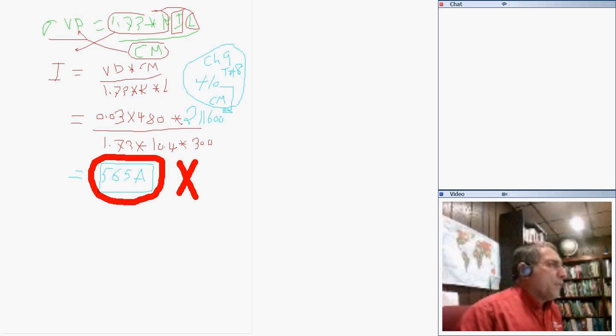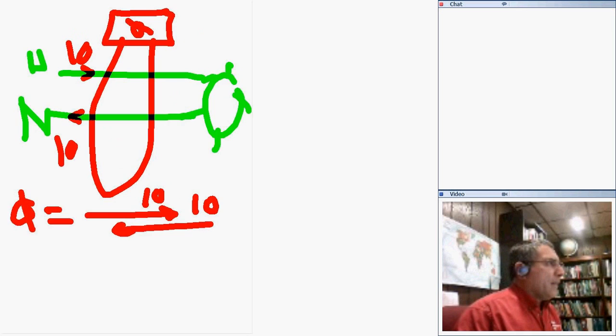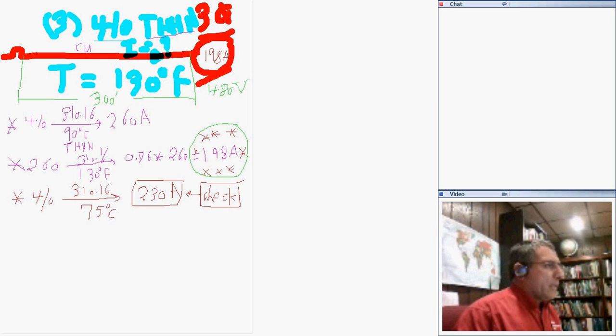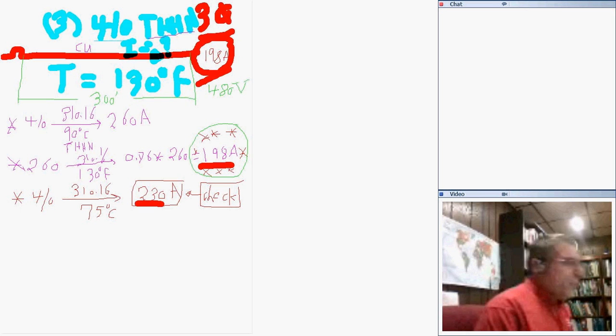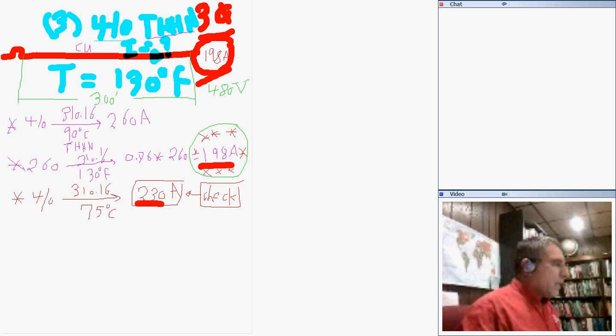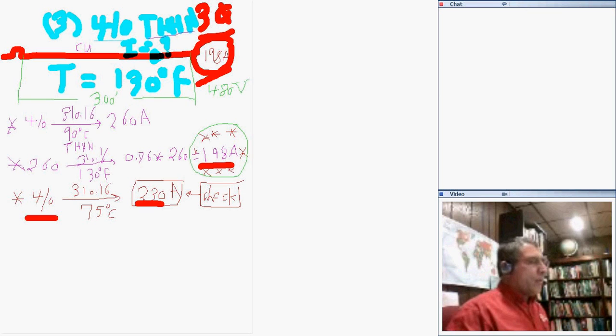That's what you guys come up with sometimes when you do the voltage drop calculation, especially at high voltage. I want to emphasize, guys, the voltage that we are using here is a very high voltage, and you end up with an amp that doesn't make sense. You can't use it. You still have to adhere to the rules. That's what I came up with, my friend. And 230. A 4/0 conductor shall not carry more than 230 amps no matter what. So if you came up with something weird like 565 amps, you can't use it, because you are still limited to 230 amps or less.